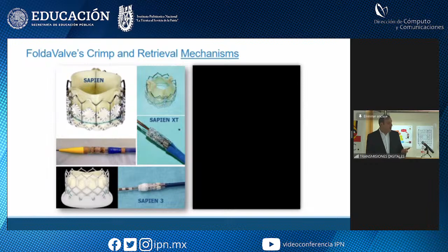Next slide, please. We have also done a lot of imaging to see how the flow changes. For example, this is flow downstream of the FoldaValve using laser PIV at 1,000 frames per second. You can see the vortices in the sinuses of Valsalva. You see how the flow is rotating, meaning this is really good for the oxygen to come back to the coronary system.